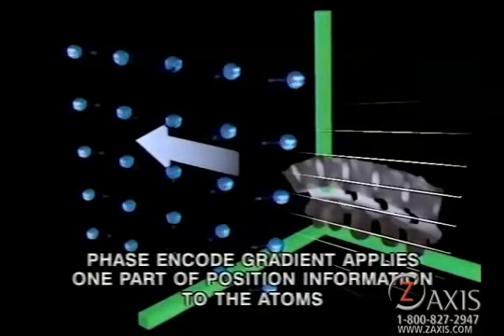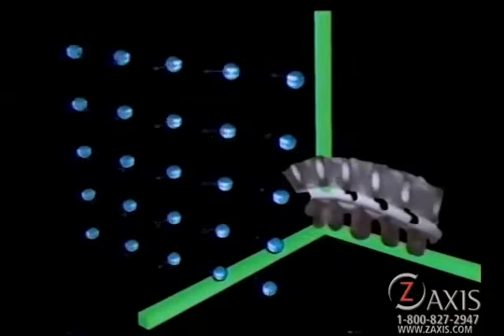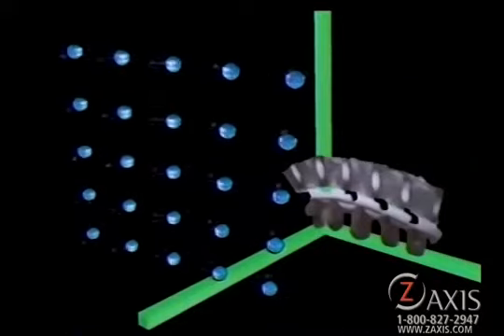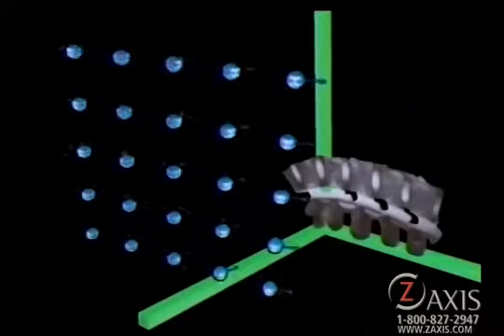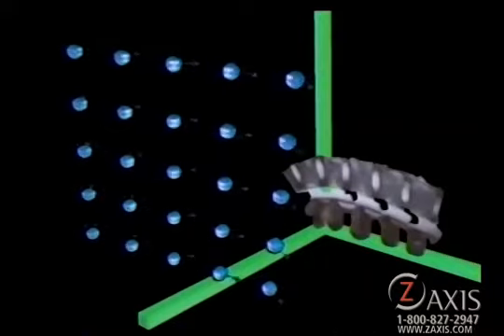A magnetic gradient, which is just a magnetic field that varies in strength from weak to strong, is applied in the direction of the arrow to force the protons to spin at different phases depending upon the strength of this new magnetic gradient. The different phases will be used to determine the proton's position along the z-axis of the patient.